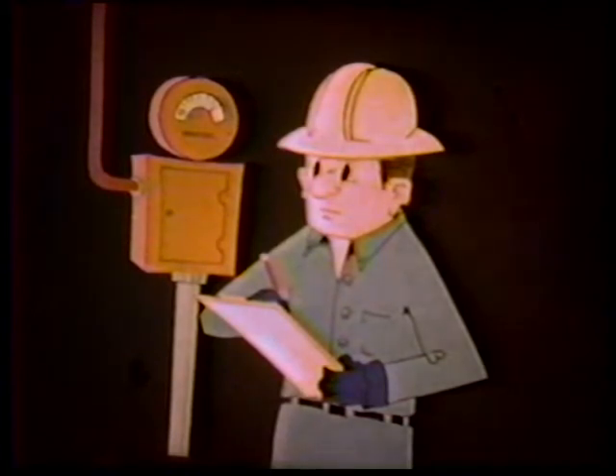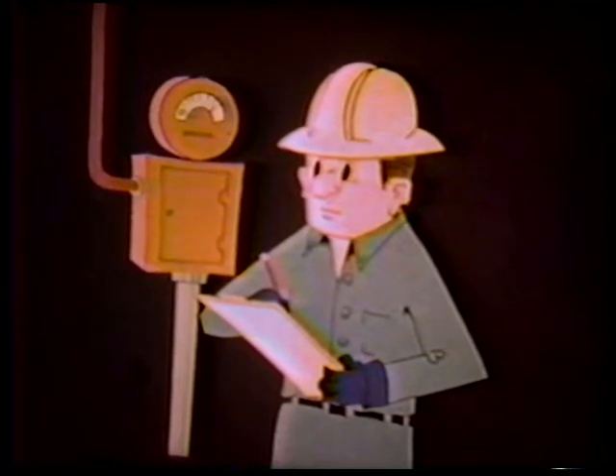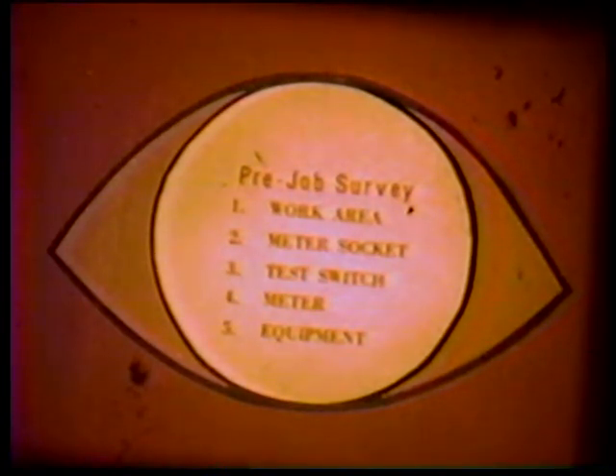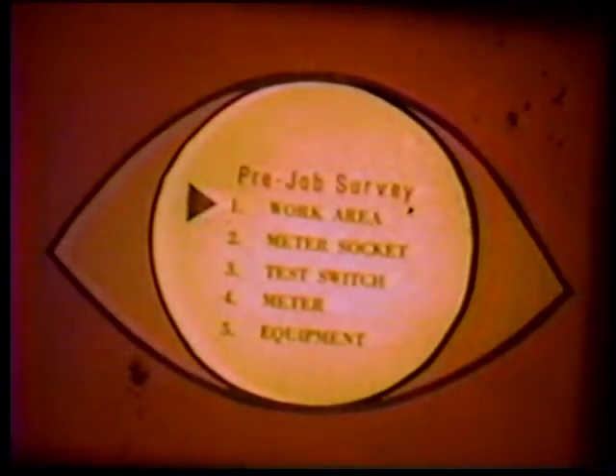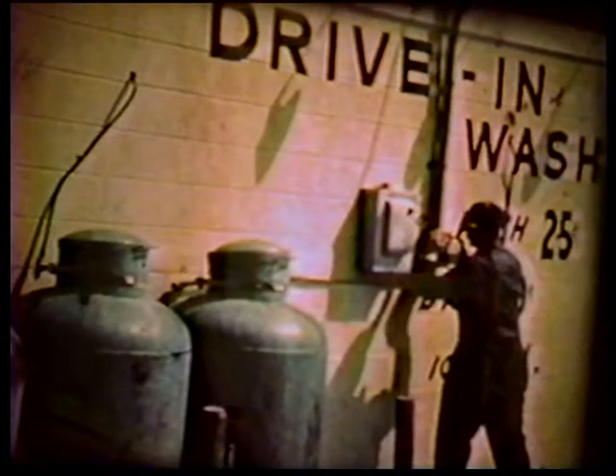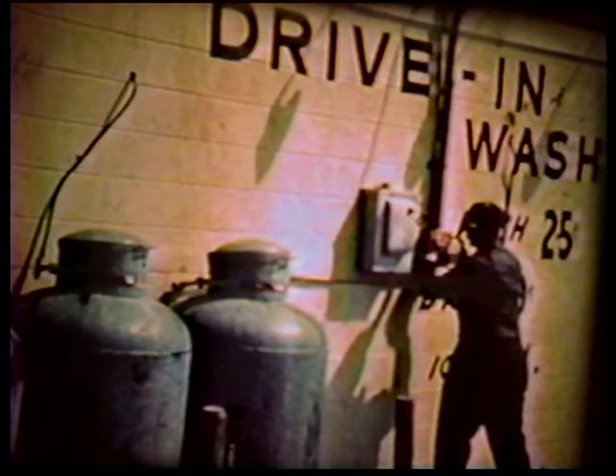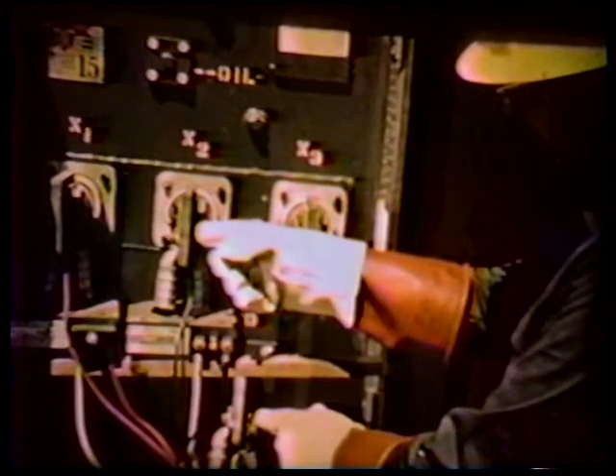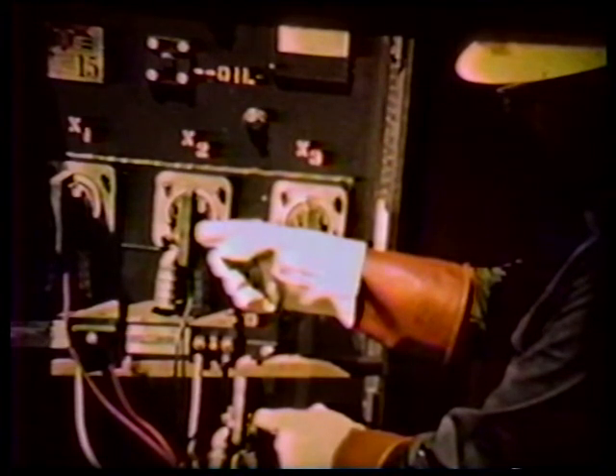Well, by analyzing the situation and planning the work step by step, you can avoid these hazards and use the safeguards to keep the hazards from becoming an accident. This planning is the mark of a master craftsman and will enable you to work more efficiently and safely. The pre-job survey can be divided into 5 major parts: work area, meter socket, test switch, meter, and equipment and materials. Survey the work area. Consider the accessibility of the meter and the condition of the surroundings. Check for flammable liquids or gases which could be explosive in the event of a flash. Consider the proximity of exposed live parts and ground.